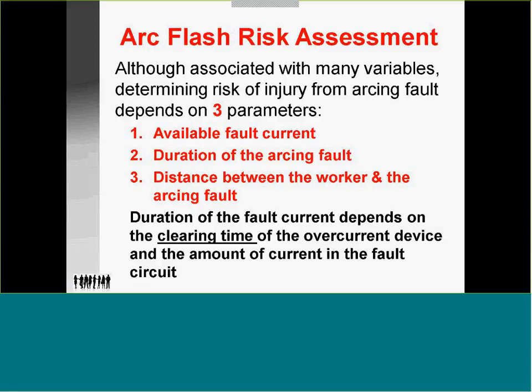Now, parameters are out there for assessment. The fault current, as I said before, is coming from the power company. What is it where it enters the property line? Now, the duration of the arcing fault. If the arc is in the main and is controlled by the breaker on the pole or by computer from the power company, it can be anywhere from 2 or 3 cycles up to 6 to 10 full seconds, which can be a tremendous burn time.